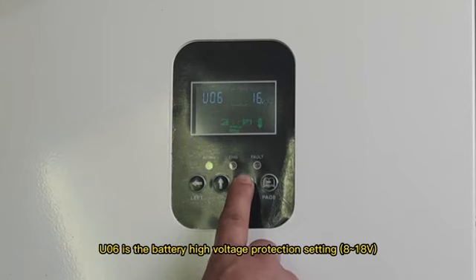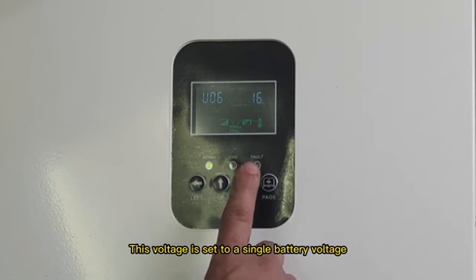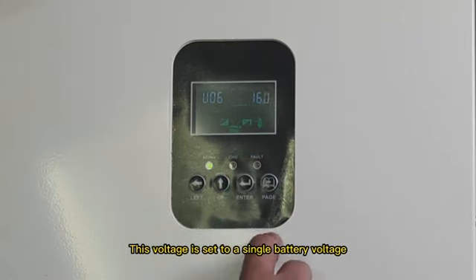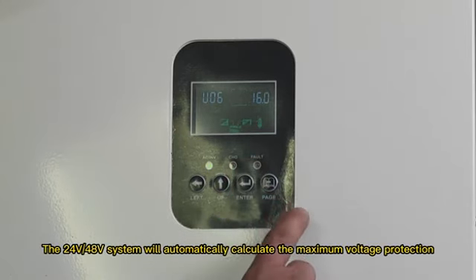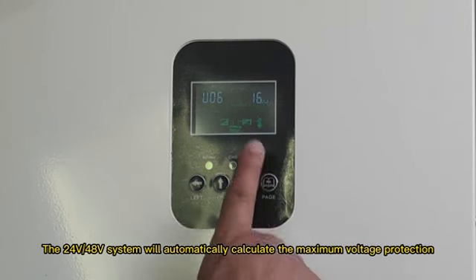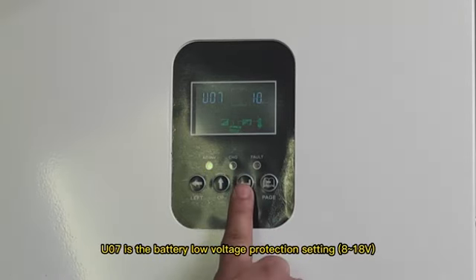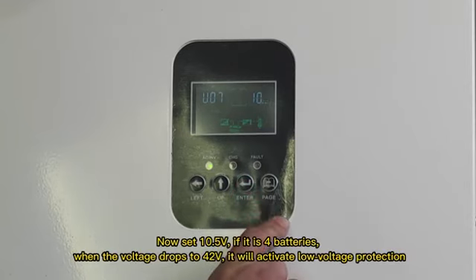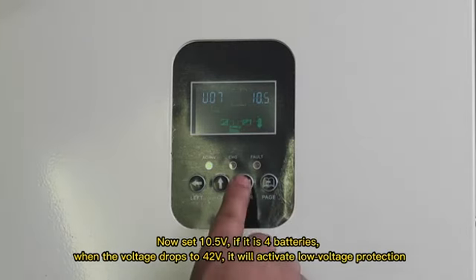U06 is the battery high voltage protection setting, 8 to 18 volts. This voltage is set to a single battery voltage. The 24V and 48V systems will automatically calculate the maximum voltage protection. U07 is the battery low voltage protection setting, 8 to 18 volts. Now set 10.5 volts, if it is 4 batteries. When the voltage drops to 42 volts, it will activate low voltage protection.